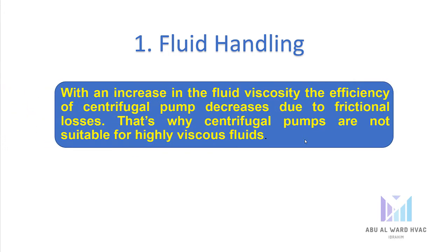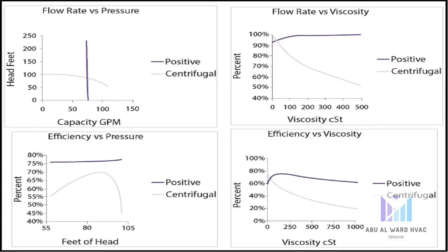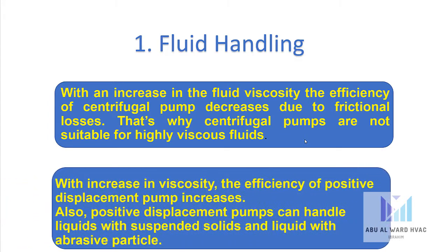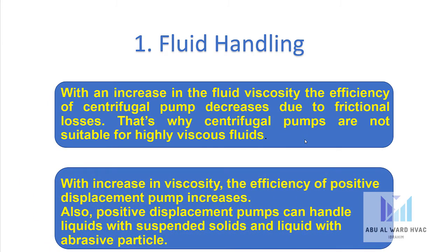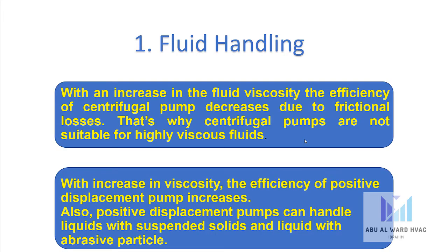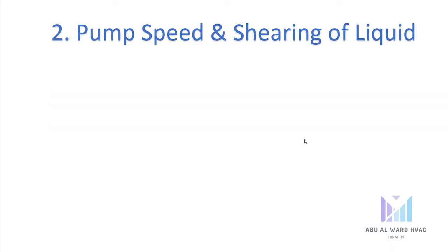With an increase in fluid viscosity, the efficiency of a centrifugal pump decreases due to frictional losses — that's why centrifugal pumps are not suitable for highly viscous fluids. With an increase in viscosity, the efficiency of a positive displacement pump increases. Also, positive displacement pumps can handle liquids with suspended solids and abrasive particles.